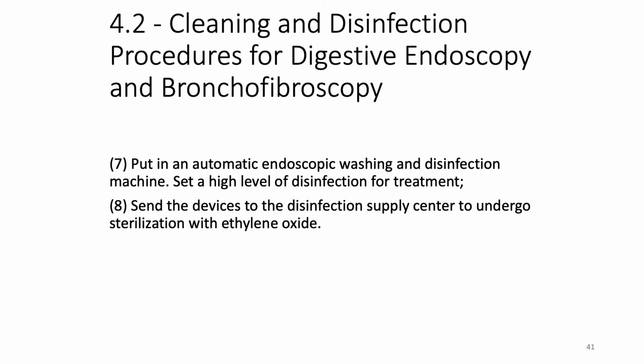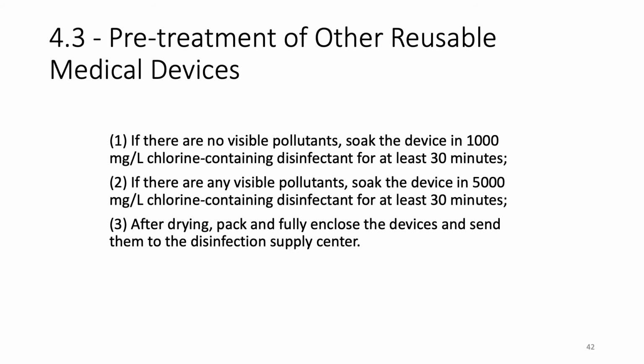So 7, put an automatic endoscopic washing and disinfection machine. Set up a high level of disinfection for treatment. 8, send the devices to the disinfection supply centre to undergo sterilisation with ethylene oxide. 4.3, pre-treatment of other reusable medical devices.